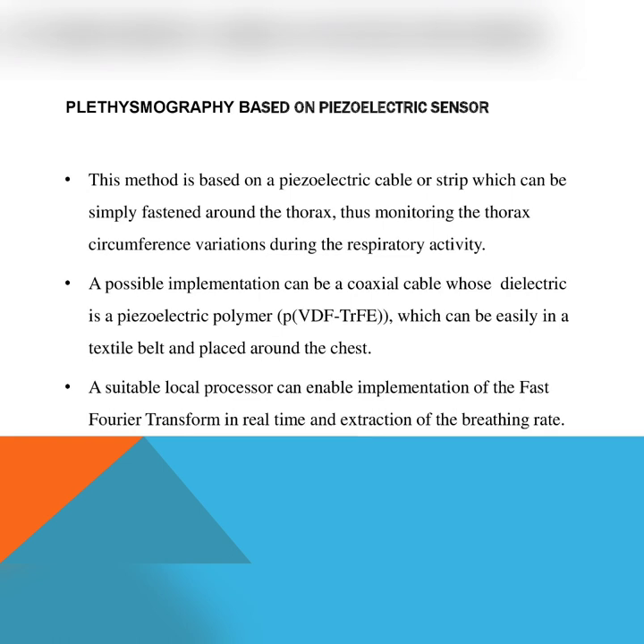Another method is based on a piezoelectric cable or strip which can simply be fastened around the thorax, thus monitoring the thorax circumference variation during the respiration activity. A possible implementation is a coaxial cable whose dielectric is a piezoelectric polymer, which can be easily built into textiles and placed around the chest. A suitable local processor can enable implementation of fast Fourier transform in real time and extraction of breathing rate. This is the concept of a wearable system equipped with a piezoelectric band.